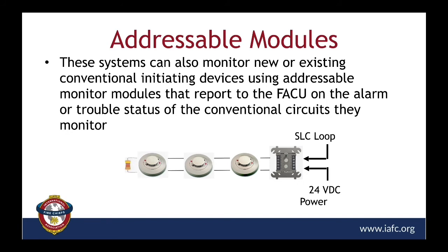In addition to the devices that Richard was talking about, such as manual pull stations, smoke detectors, and duct detectors, all of these can be addressable devices and come in as a single address or a single point. But when it comes to monitoring conventional devices, probably the most common is your water flow switch, your tamper switch on the OS&Y valve, and you could have some conventional smoke detectors in an application that you want to bring into that addressable fire alarm panel.